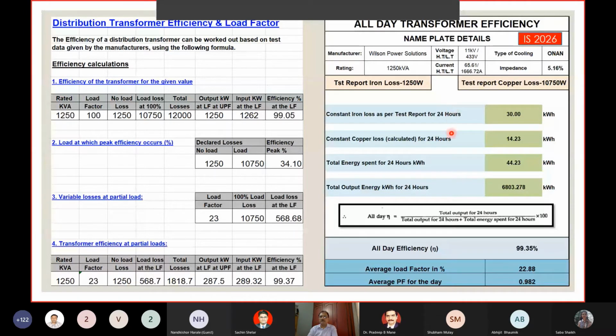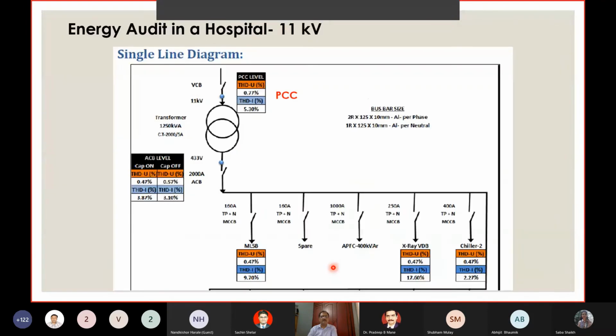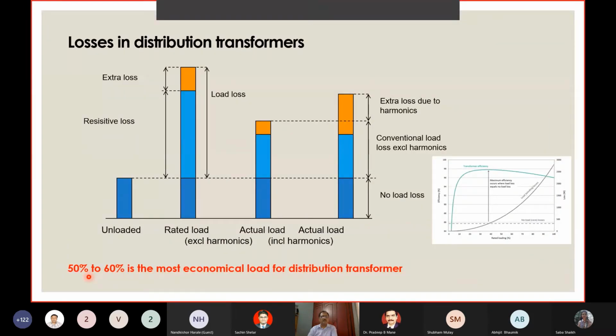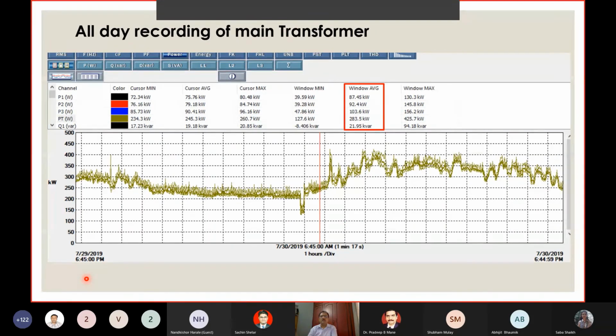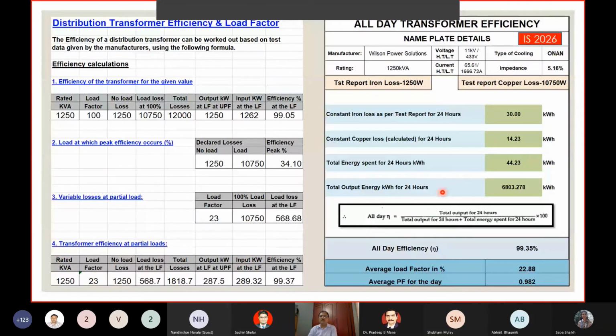So can we improve this 99.35? No. But can we improve the load factor? Yes. Because in the previous slide we saw that the most economical load factor can be 50 to 60%. So it's possible for this hospital to expand and still load this transformer better and retain this efficiency better. So this is one of our findings.